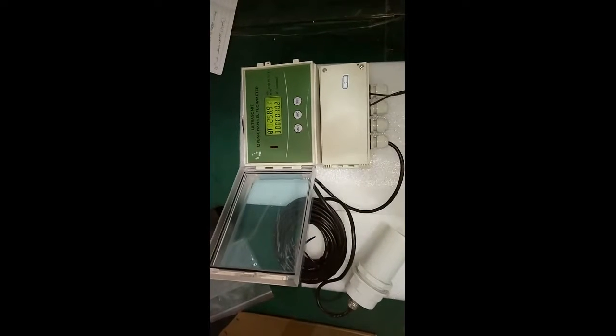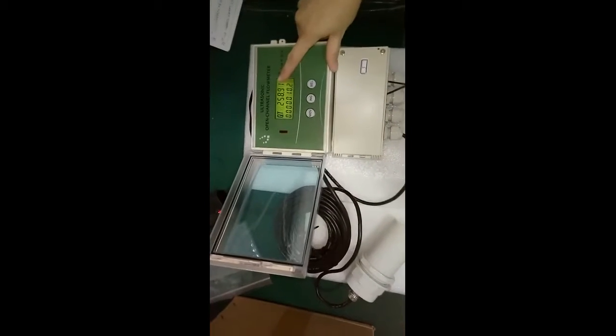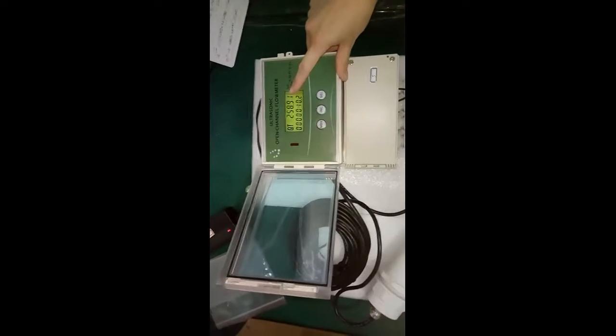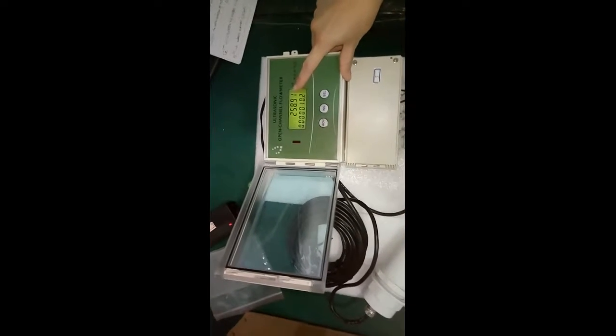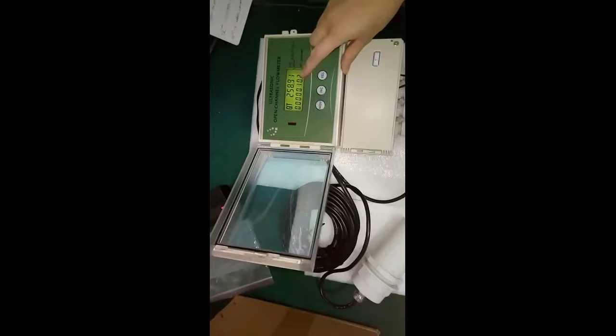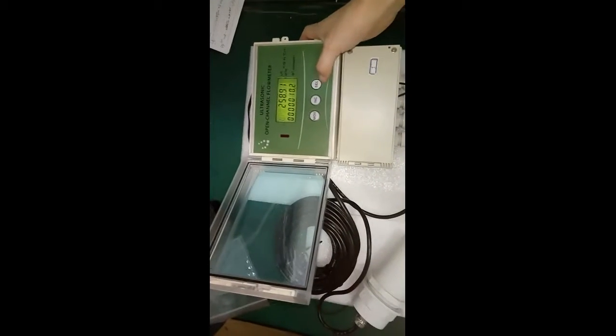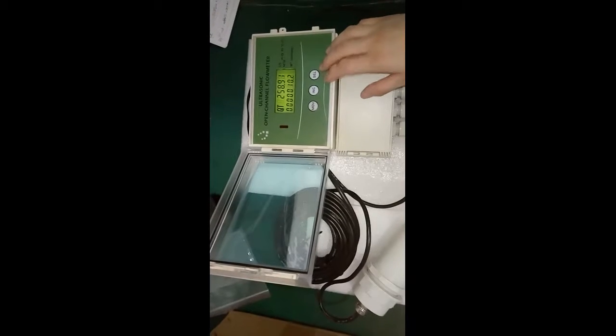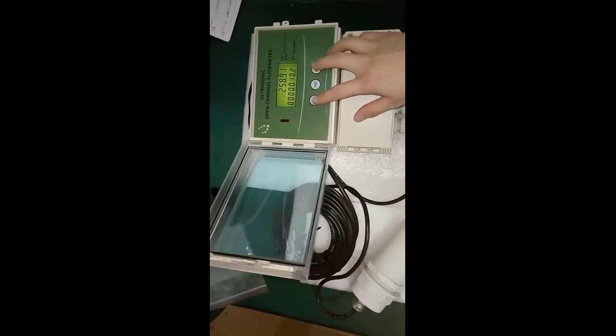This is the Ultrasonic open channel flow meter. Now I will show how to operate it. First, this is the home page. The QT is instantaneous flow rate, this is the totalizer. Now enter the select and move key at the same time.